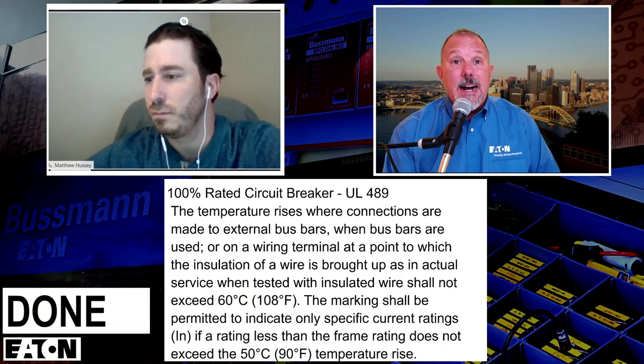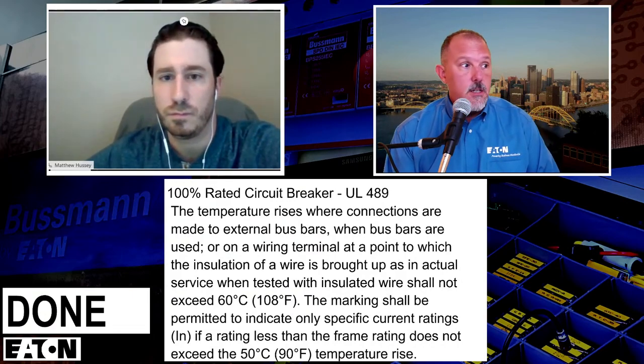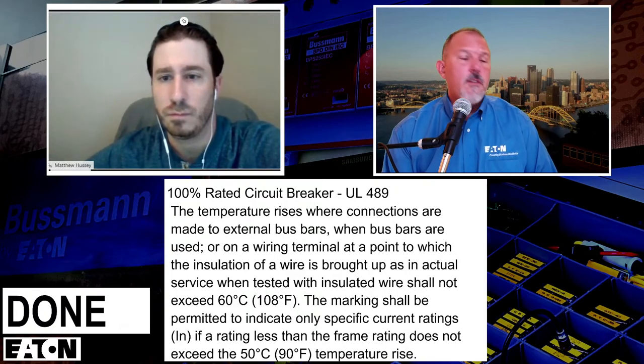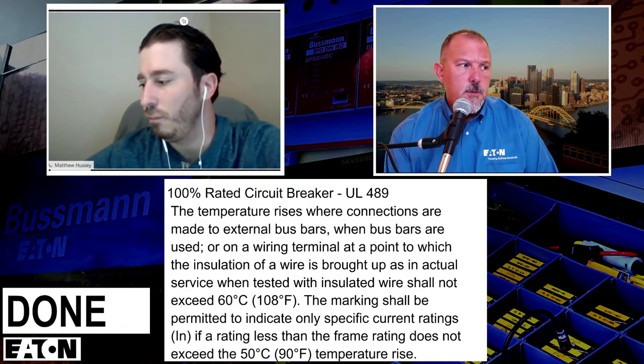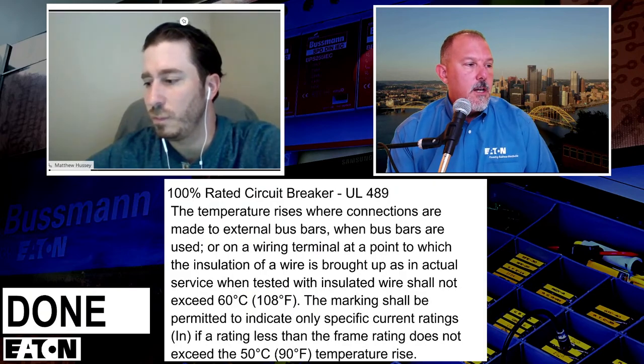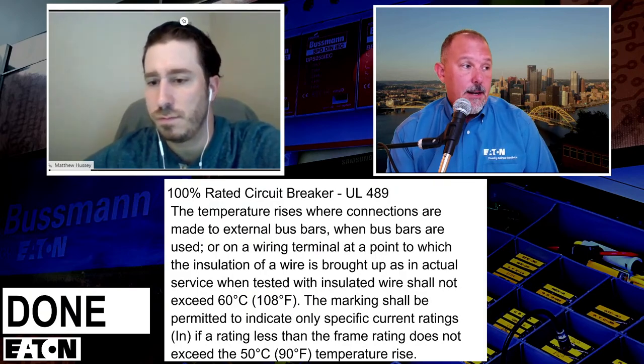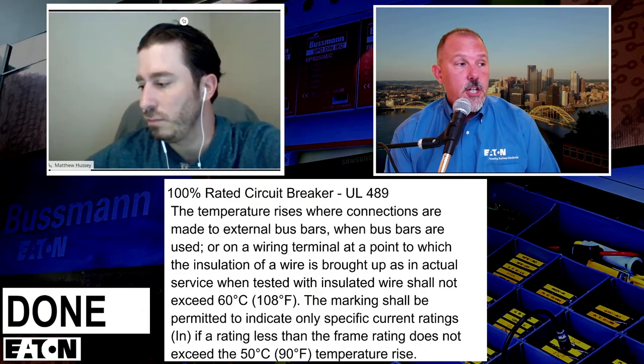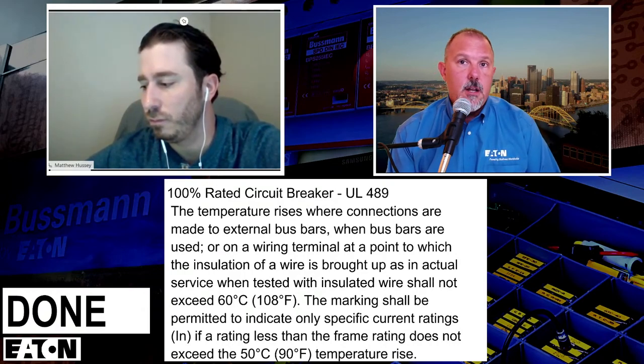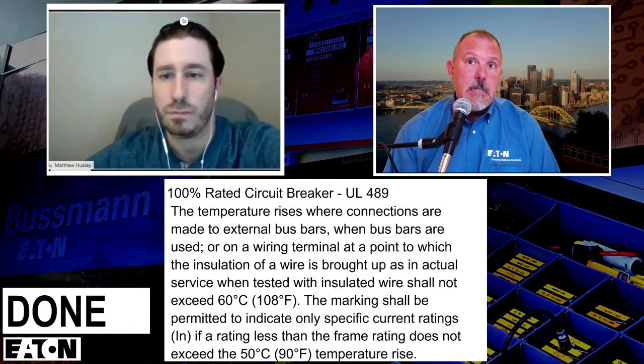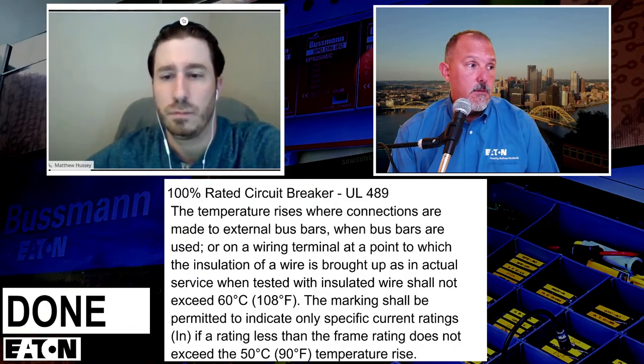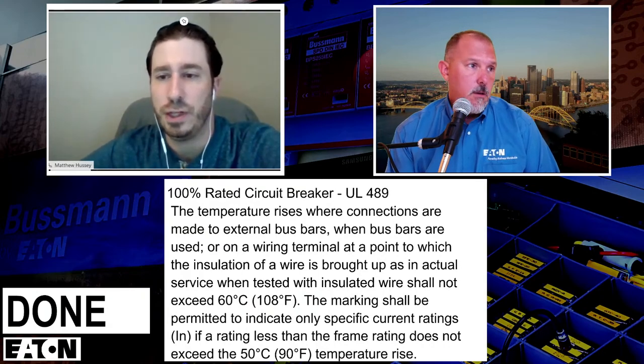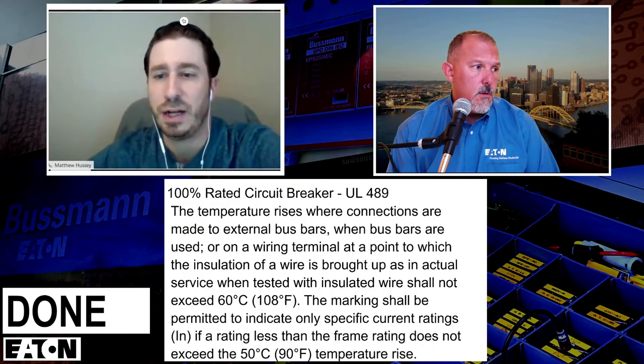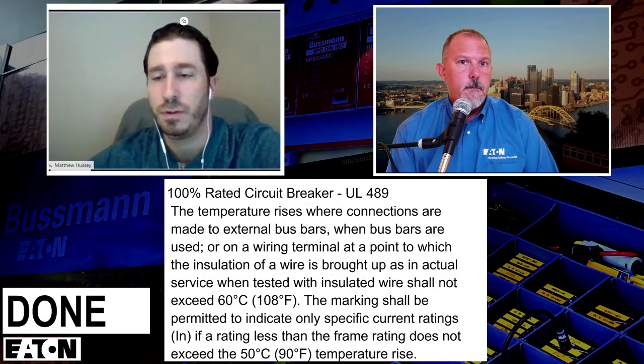it's all about the heat and the rise on certain terminations. I'm not as familiar with hydraulic magnetic breakers, so I don't know how to answer that question, but I can say that we change the lugs, we change a lot of other things. It's not just about what's inside the circuit breaker that counts. And also, the circuit breaker would need to be calibrated to have its time current curve dependent upon that type of application as well.